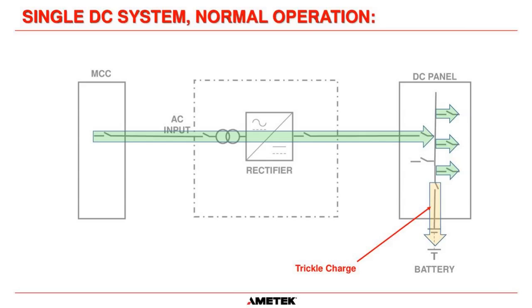So what I'm going to do is go through the power flow for a DC system and show you how the power is flowing through the load circuits and the battery in each example. In normal operation, your MCC is going to feed into your rectifier through its AC input breaker, and it's going to change the AC into DC within the rectifier charger.